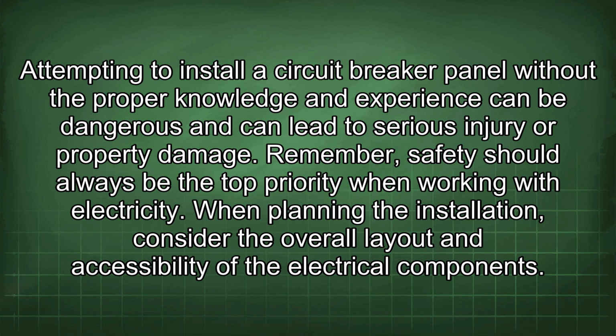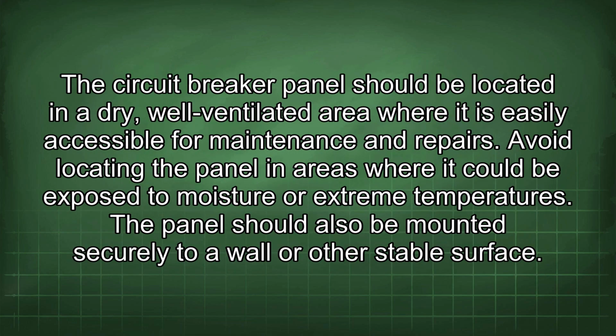When planning the installation, consider the overall layout and accessibility of the electrical components. The circuit breaker panel should be located in a dry, well-ventilated area where it is easily accessible for maintenance and repairs. Avoid locating the panel in areas where it could be exposed to moisture or extreme temperatures. The panel should also be mounted securely to a wall or other stable surface.